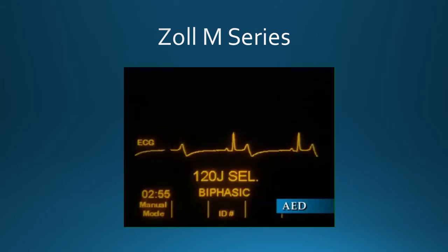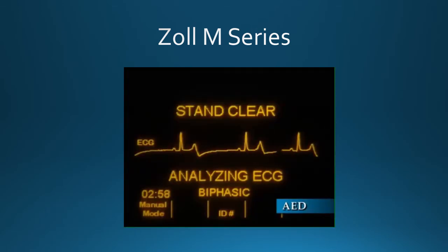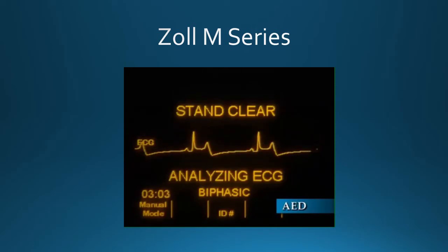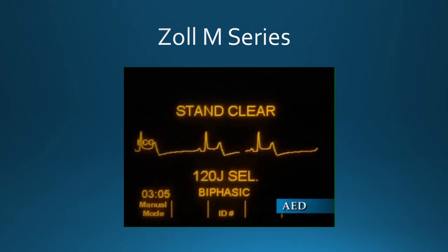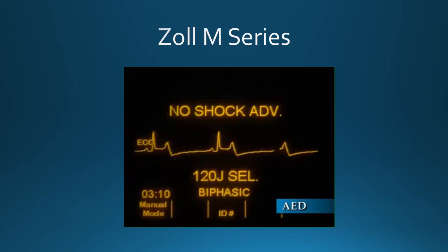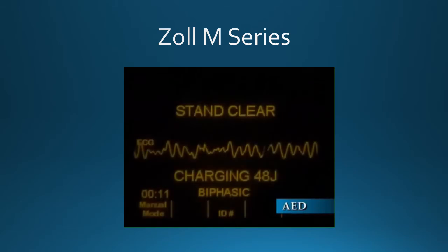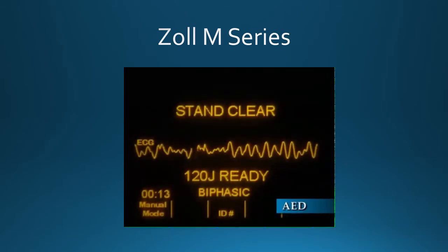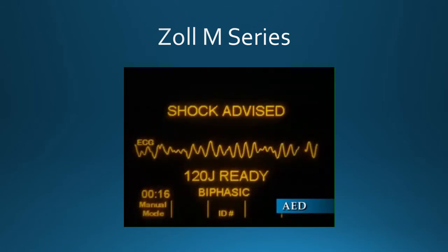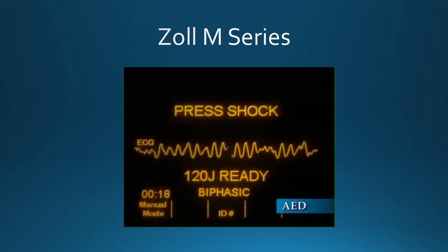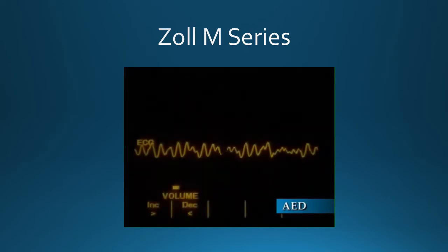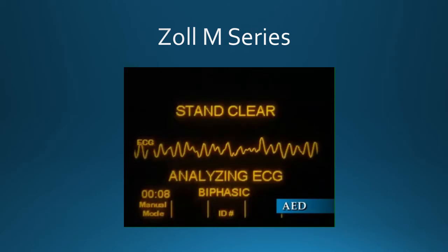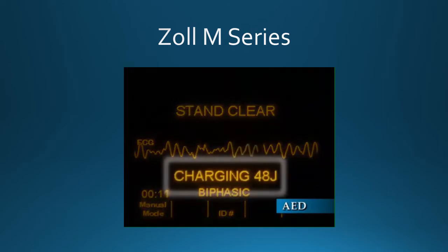When analysis is complete, the unit indicates whether or not a shock is advised. Stand clear. When a non-shockable rhythm is detected, the No Shock Advised message and voice prompt are issued. No shock advised. Immediately check the patient's pulse and breathing and resume other treatment per protocol. If the patient's rhythm is shockable, the unit will display a Shock Advised message. Press shock. If so configured, the defibrillator will automatically begin charging to the pre-selected energy setting and display a charging message.